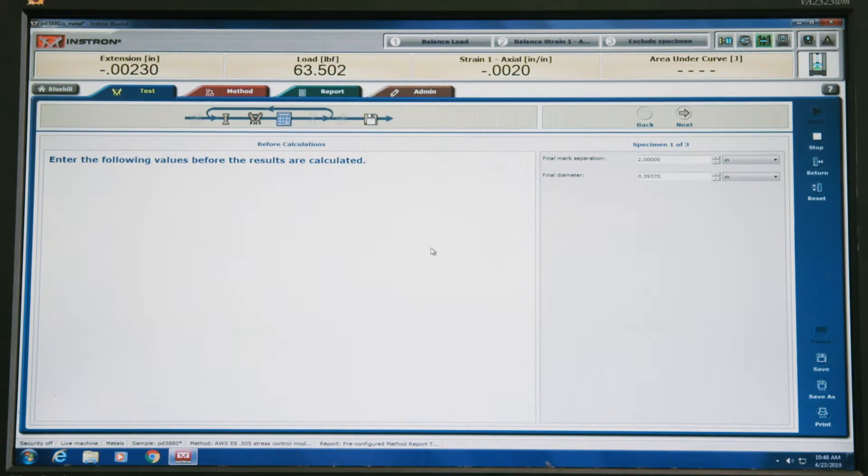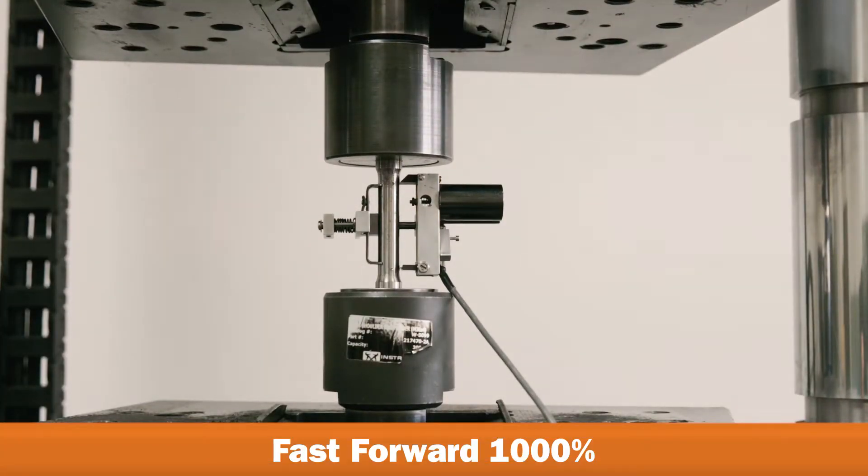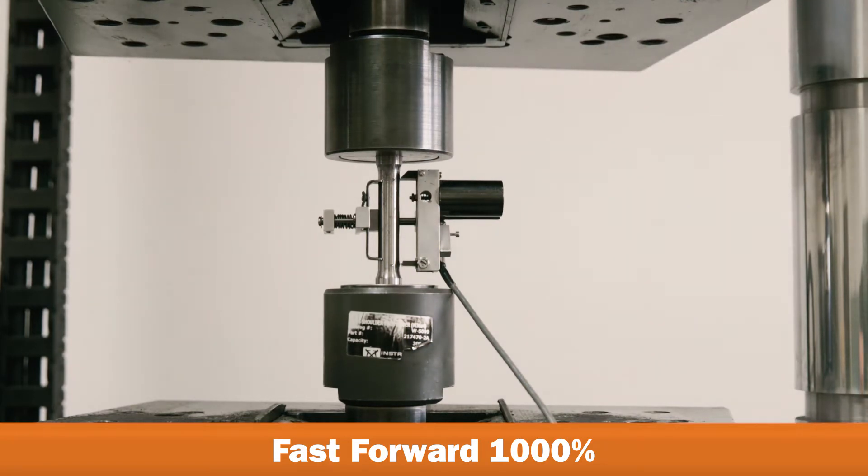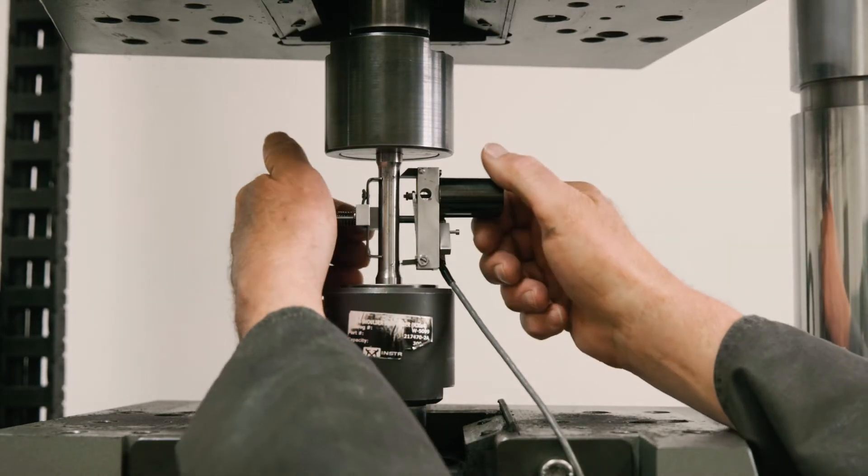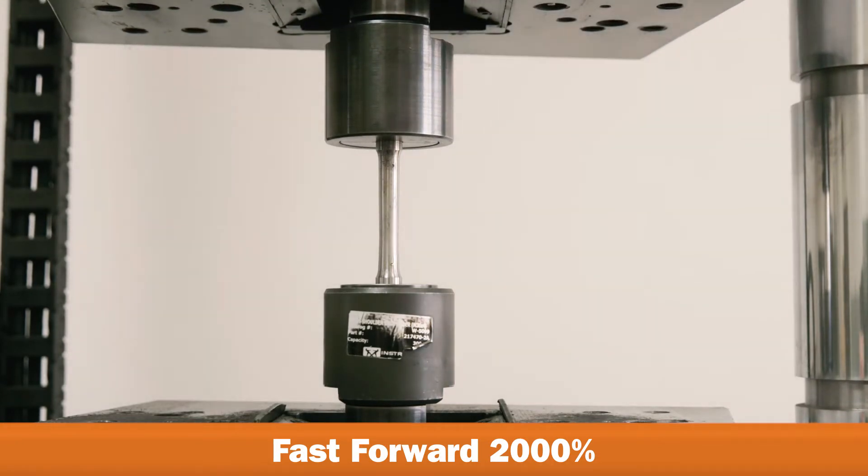The technician then initiates the test. The crossheads begin pulling in opposite directions. Until the yield point has been reached, there is no plastic deformation of the sample. Once the material has reached its yield point, the extensometer is removed. The test then resumes until the material fails.